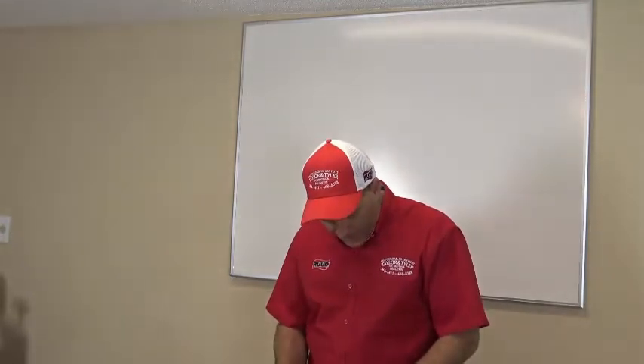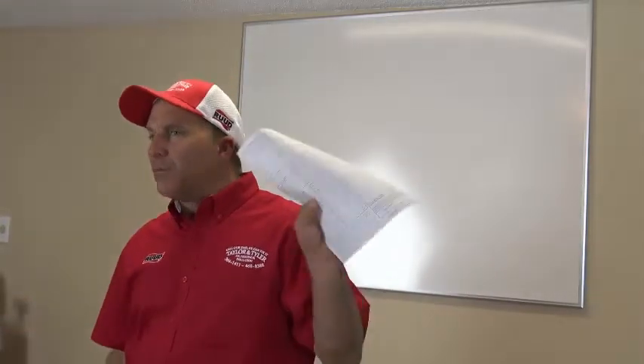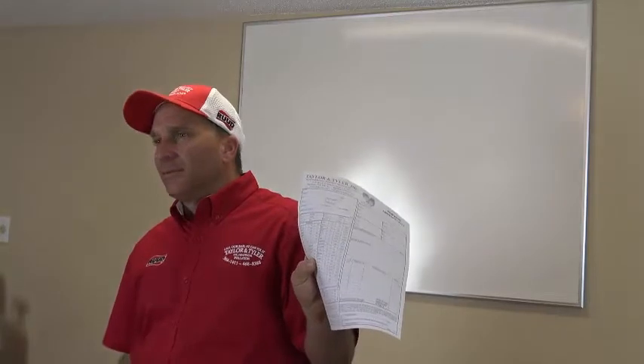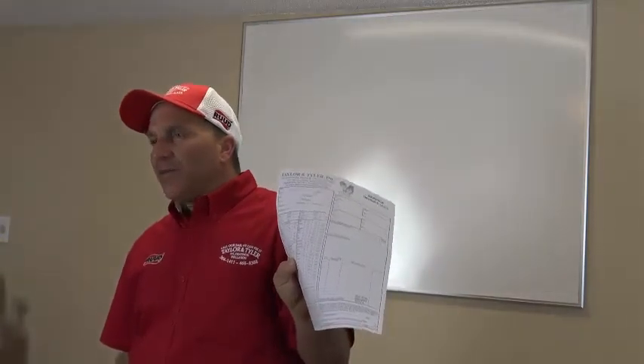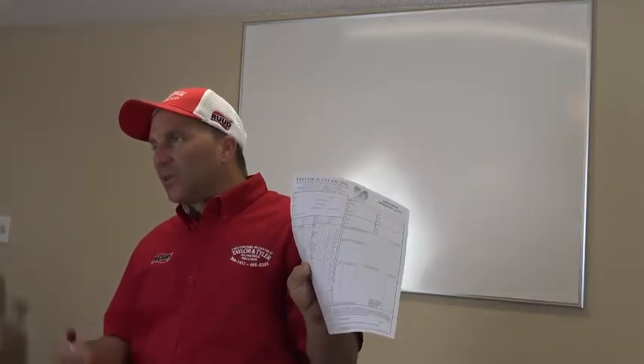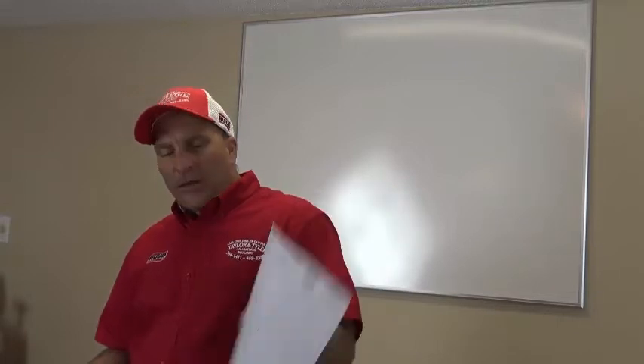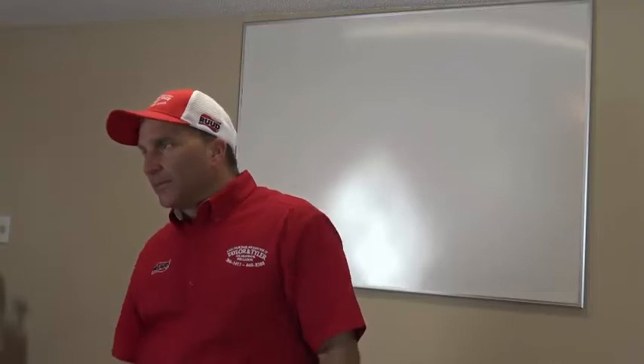All right, your electrical whip, wrong size or is it burned? How about if it's hanging off the wall, if the whip is too long, if it's curled up at the end of the condenser, if it's a 1/2-inch whip on a 5-ton system, is it not strapped to the wall? Read more into that. If the whip is extremely too long, then you can just write over the top of that line, too long.